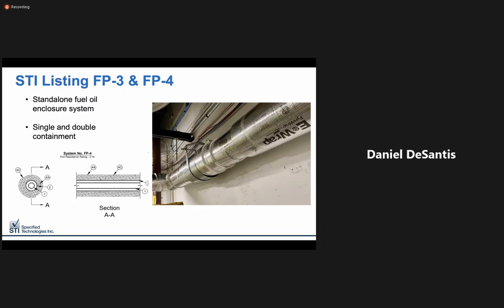Like the previous Intertech system, the material is applied in layers corresponding to the required hourly rating. On this 8-inch diameter fuel oil line shown, 4 layers were being installed telescopically to achieve a 2-hour rated enclosure.